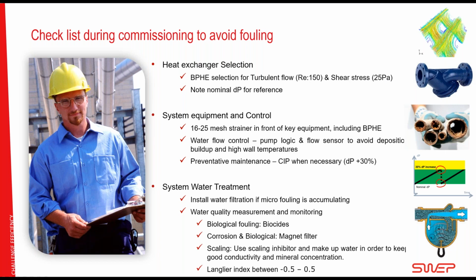Note the starting point of pressure drop when you commission the system. Use a strainer of about 16 to 25 mesh. The smaller the heat exchanger, so to say, the higher the mesh number in some way. That one will stop the blocking.